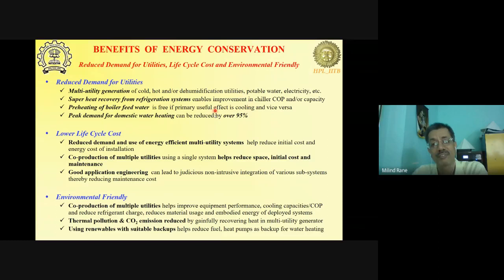In fact, we have also talked about making the demand negative. That is actually saving power for the AC, as compared to solar, which can only save you electricity for heating or energy for heating the water. But superheat recovery can not only give you free hot water, it can also reduce the power consumption of the AC. So that's the bigger benefit, and that too with very little maintenance.